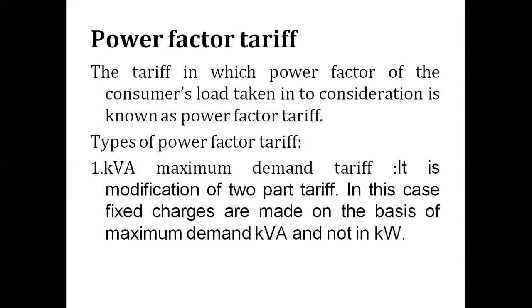There are different types of Power Factor Tariff. The first one is the KVA Maximum Demand Tariff. It is a modification of the Two-Part Tariff where fixed charges are made on the basis of Maximum Demand in KVA, not in kilowatts. This type of tariff has the advantage that it encourages consumers to operate their appliances and machinery at a high input power factor.